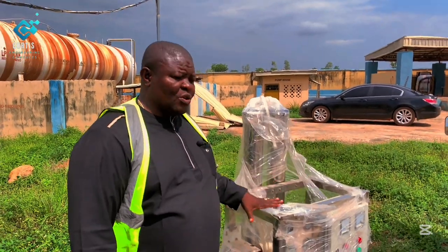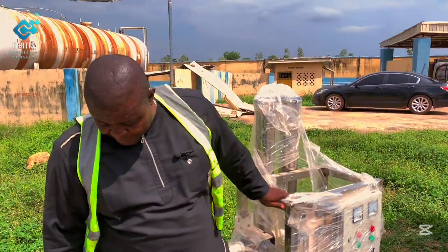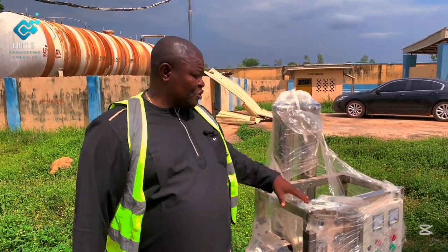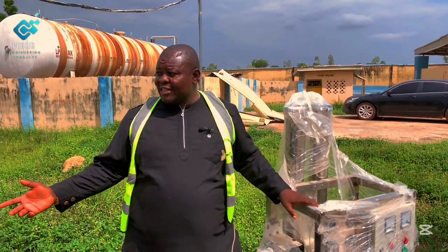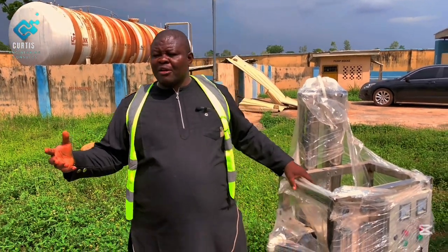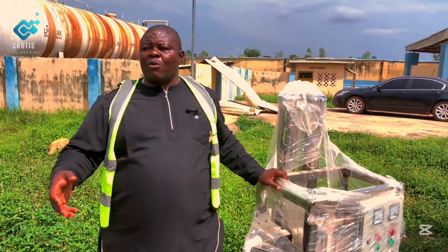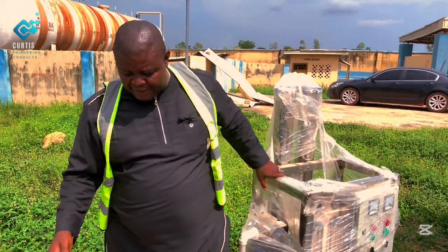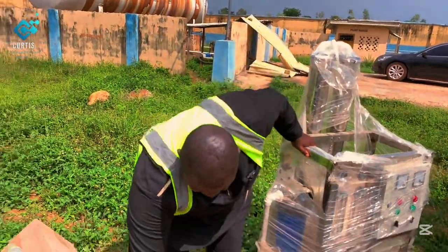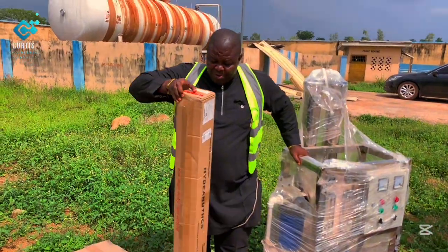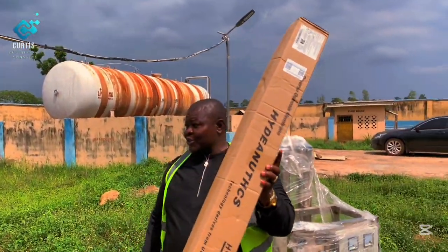Because of the salt and the deposit, there's also knowledge I want to share with us: even if you have this reverse osmosis system and you don't use the right membrane, it becomes a challenge, because some membranes are just designed to treat surface water or any other water that contains other pollutants. But if it is salt and iron, you need to bring a membrane that is specific for salt and iron.